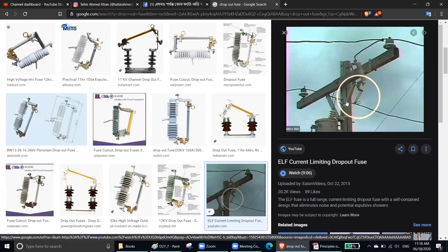Yes, sir, okay, lightning arrestor is a different thing. The lightning arrestor takes out the excessive amount of voltage and releases it to the ground, that's its only principle, very simple. When voltage is normal, the resistivity is much higher, almost infinite, meaning an open circuit. But when the voltage is much bigger, the resistivity is 0, so it's a short circuit, and the highest amount of voltage discharges to the ground. So it will not move elsewhere, it will just go to the ground directly. Got my point? So what is a dropout fuse? Yes, sir, I will check and let you know, inshallah.